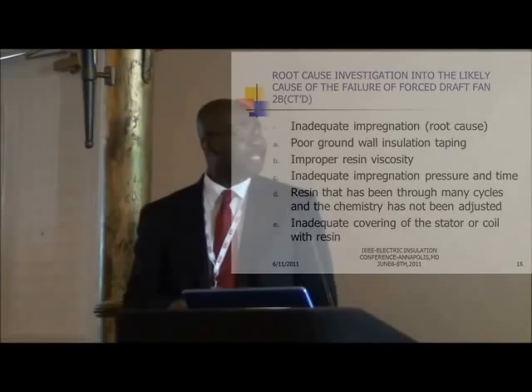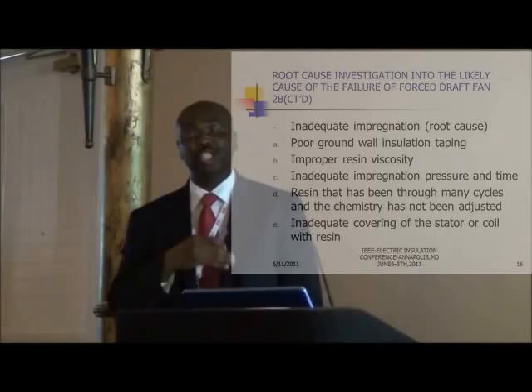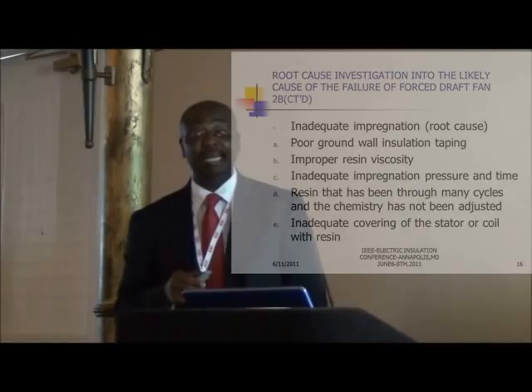Inadequate impregnation is another root cause. Without proper impregnation, the ground wall insulation taping begins to fail. We found that the resin in the motor shop was not being changed properly — old resin was being reused, and the impregnation pressure time was not adequate. These factors compromised the integrity of the winding insulation.